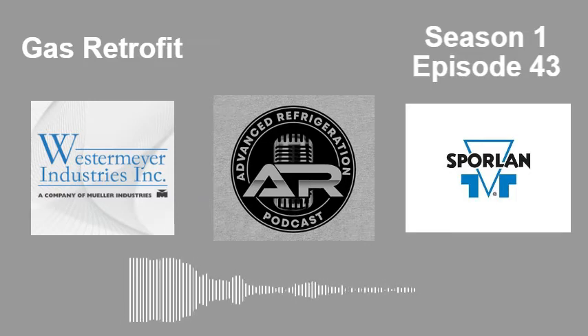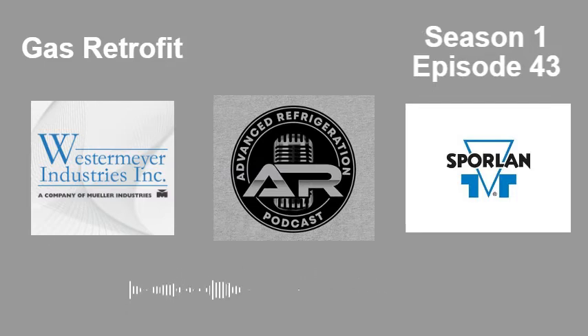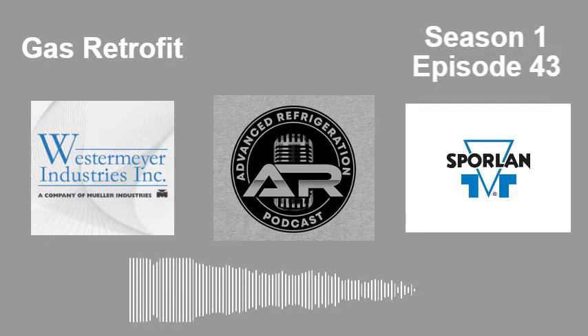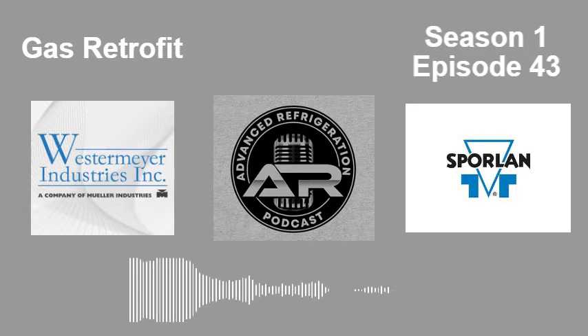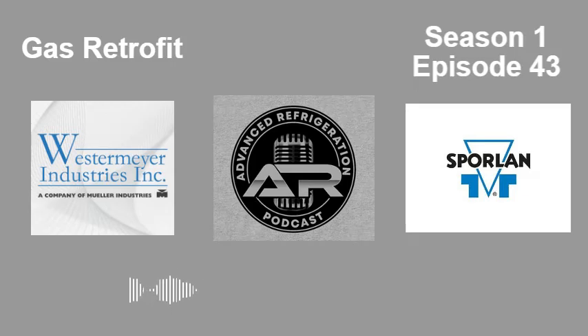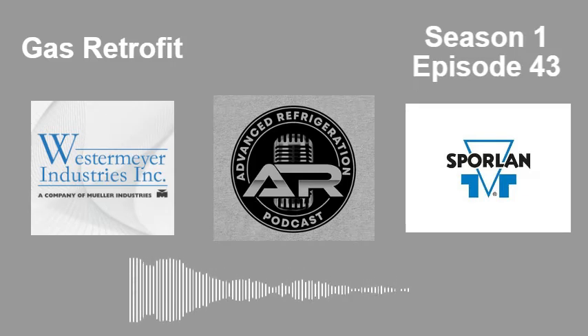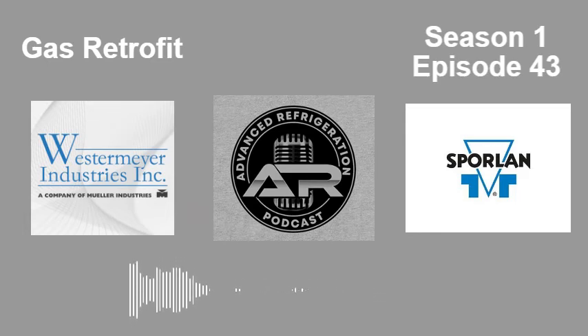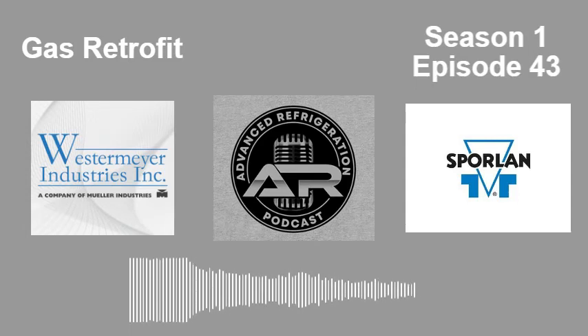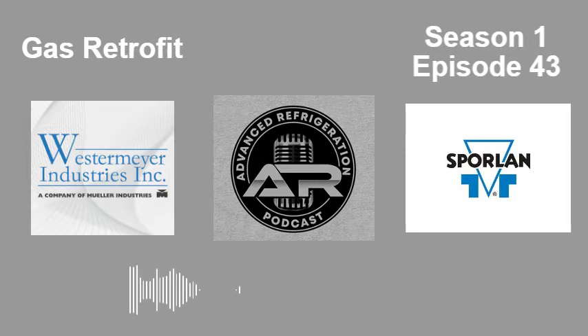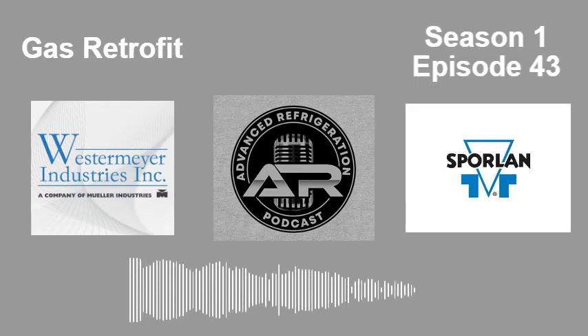Copeland's, you aren't going to have that problem. Bitzers, same thing. As you start doing these oil changes, after you drain the first compressor down, get it all cleaned up, get it ready to go, fill it back up with oil. Go to the next compressor, drain it down, do the same thing, fill it back up with oil. Keep going on all of them. As you're moving to drain the reservoir down, you're filling up with oil. By the time you get to the last one, the change is done. You'll let it circulate for the next day while you're doing another rack or something else.